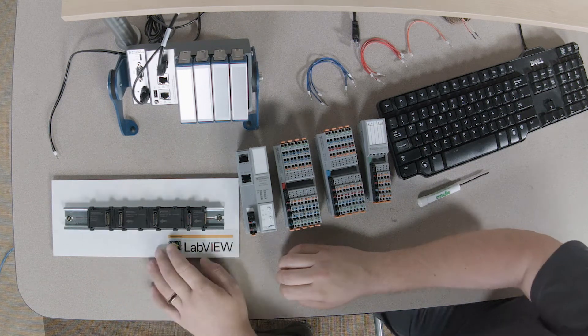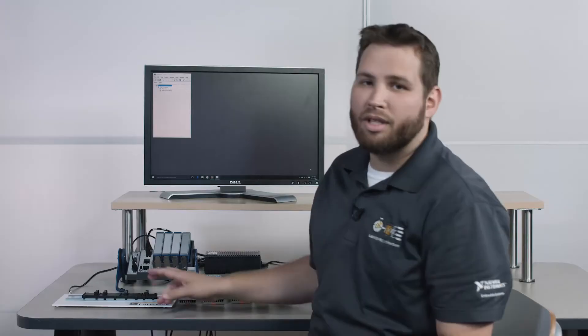Now, I want to pause here and talk briefly about this digital backplane that we basically built on the DIN rail. It's a fully shielded backplane, and what that means is that it's much more noise immune. So that lets us run the digital back end at a higher rate. All the modules update faster. The signal path for analog is quieter, so you get a better analog measurement, and it happens to be particularly robust in terms of shock and vibration.